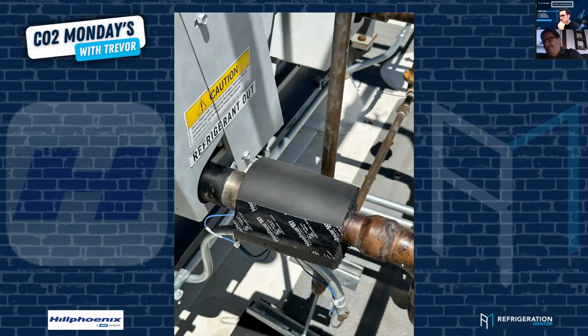So this here looks like the outlet drop leg. Oh yeah, the contractor had some gum tape around it, so I took a thermal picture of it. I wish I had sent that to you, Trevor, where the gum was 90 degrees, the pipe was 72 degrees. So what do you think the temperature was? Probably closer to 90 degrees. Because it was the valve, we were having issues with pressure and how the valve was operating. The valve was really wide open.